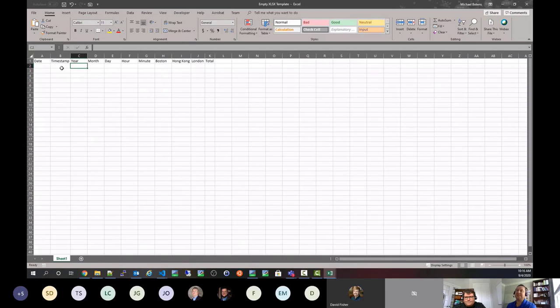What I like to do, instead of having just a single date right here, is split up the timestamp into these 5 columns, and then calculate a date and a timestamp that I'll use to filter my data appropriately. Let's say Boston is what we'll use for the timestamp, because another important thing is to make sure your timestamps line up on the report. Jeff is a good follower of this because he taught me: always zero out your trend log so that it happens on the hour or on the 15 minutes or whatever, and not have things coming in at 9:42 a.m.